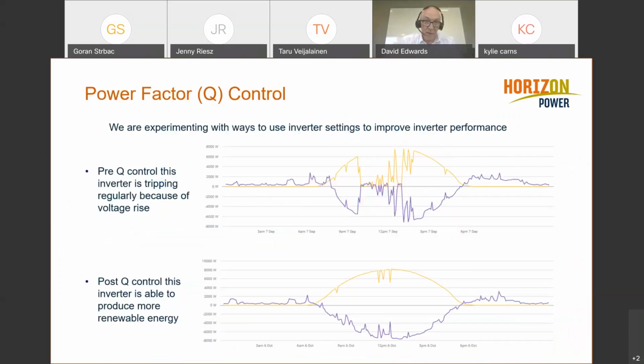So this slide shows one of those unmanaged PV systems on that particular feeder. Prior to the reactive power control, the inverter in question was unable to operate effectively because of the high volts on the feeder. But during the reactive power control experiments, the performance of the inverter was markedly improved because the voltage on that part of the feeder was improving. And this raises some really interesting questions around the usefulness of Q control to manage network voltages while we still have a significant fleet of older and unmanaged PV systems that remain connected to our networks.